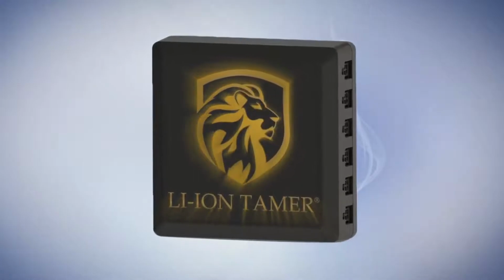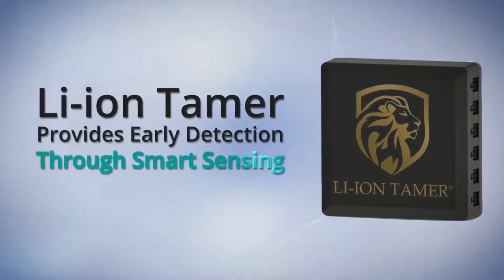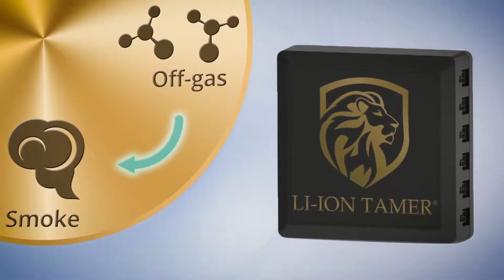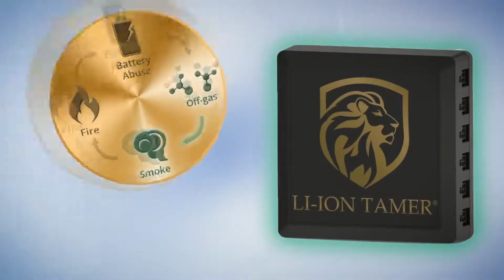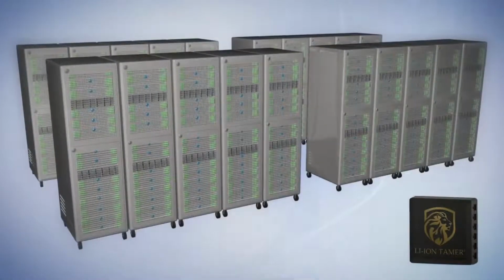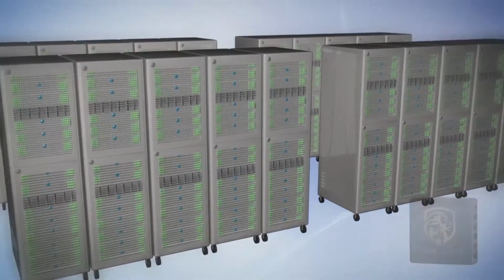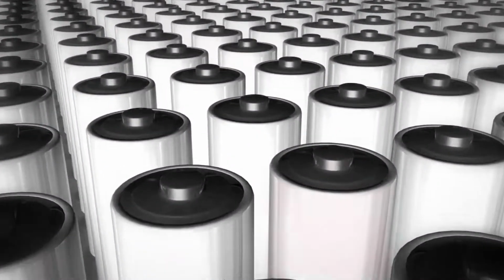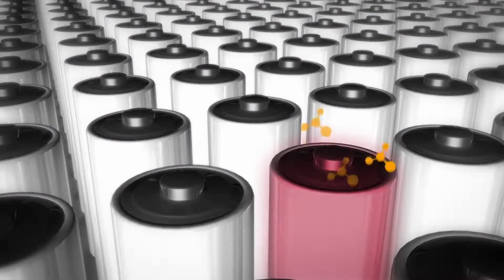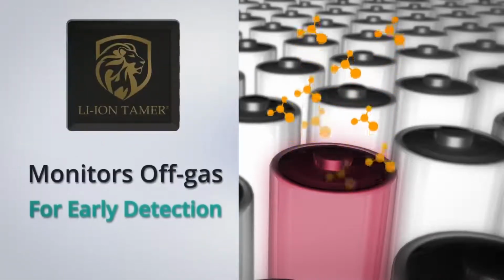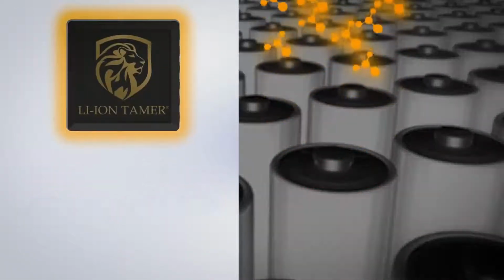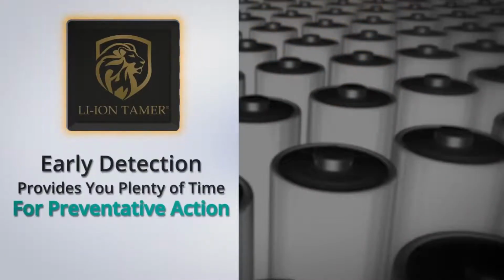Tamer is a new line of products designed to make battery storage systems safer, to provide earlier warning through smarter sensing. Tamer works at the second stage, the interval between off-gas generation and smoke, to stop thermal runaway before it ever gets started. An off-gas monitor is placed at each battery rack to monitor off-gas events. It can detect a single-cell battery failure in a typical open-air battery rack. When failing lithium-ion batteries emit off-gas, Tamer can detect this precursor before the cell fails. Now there's time to take preventative action.